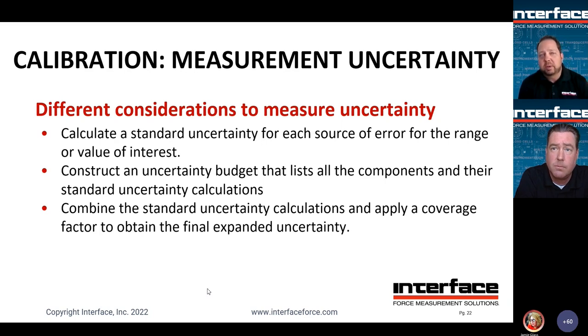The goal there is to calculate essentially an uncertainty for each source of error, right? So you're going to construct an overall uncertainty budget that lists all the components and each component's contributions to a total uncertainty. And then at the end, you may need to combine it all and apply an additional coverage factor to be able to perhaps cover a full range of desired measurements. Next slide.